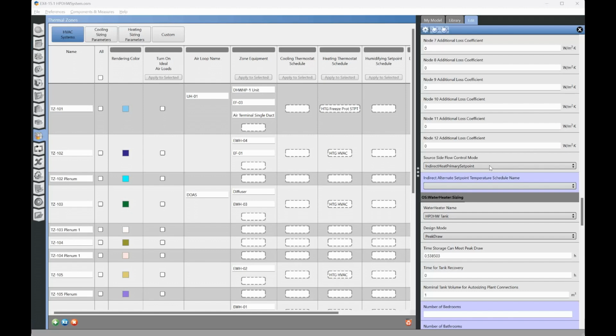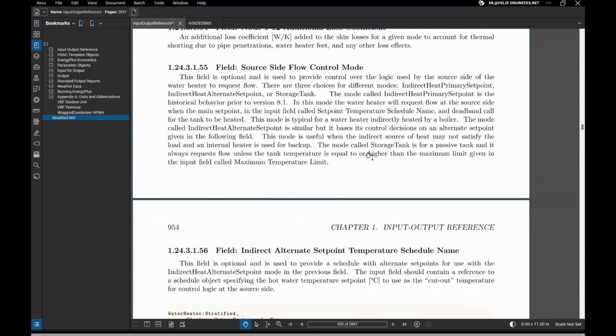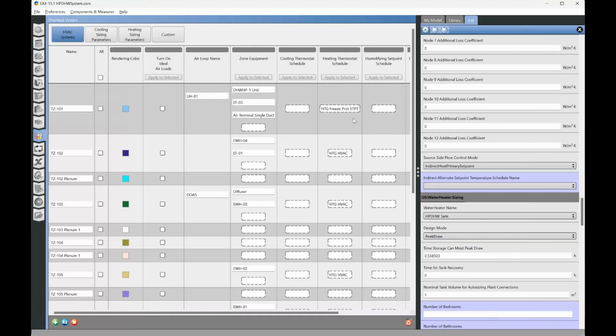The next item on the list is source side flow control mode. There are 3 different options here. Indirect heat primary set point is the default option, and again, you can read about it in the manual. This option assumes that the compressor is the primary source of heat. So the compressor runs at a high temperature, and then the heating elements turn on if the compressor is unable to heat the water in the tank.